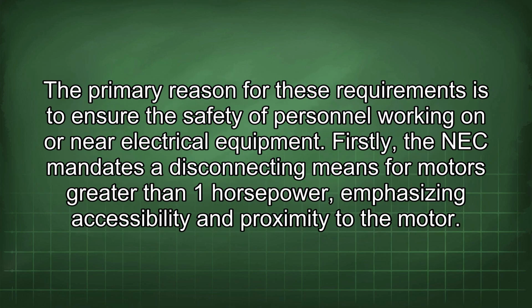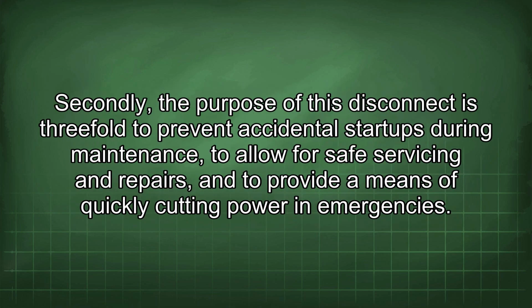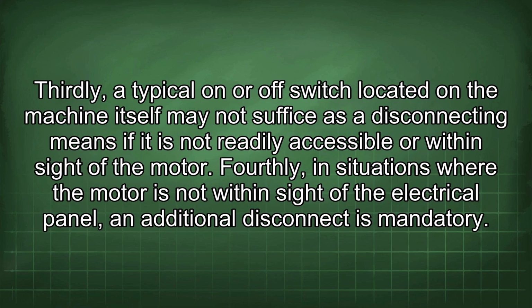The primary reason for these requirements is to ensure the safety of personnel working on or near electrical equipment. Firstly, the NEC mandates a disconnecting means for motors greater than 1 horsepower, emphasizing accessibility and proximity to the motor. Secondly, the purpose of this disconnect is threefold: to prevent accidental startups during maintenance, to allow for safe servicing and repairs, and to provide a means of quickly cutting power in emergencies. Thirdly, a typical on or off switch located on the machine itself may not suffice as a disconnecting means if it is not readily accessible or within sight of the motor.